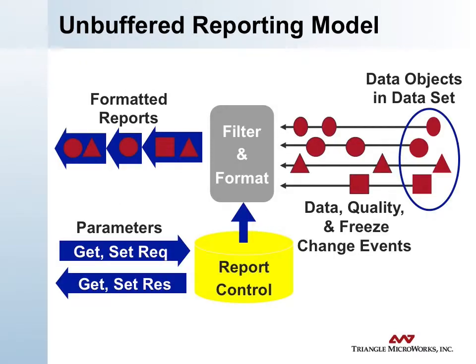This iconic view shows how the unbuffered reporting model works. On the right, we have data objects within a data set — the oval with a circle, triangle, and square inside shows the actual data objects named within the data set. As changes occur to that data, we see a flow from right to left of the values occurring as the change events occur. There's some logic within the 61850 model that does filtering and formatting of those changes, turning that sequence of changes into a sequence of messages. Each message can contain the value of one or more changes.